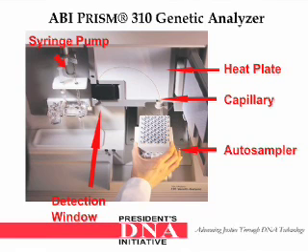Here is a depiction of the inside of the ABI Prism 310 Genetic Analyzer. On the auto-sampler is where the samples are placed. You have the capillary, which is running from the cathode to the anode. The heat plate keeps a constant temperature. The syringe pump pumps the capillaries full of polymer. And the detection window is where the emission from the laser excitation is collected.